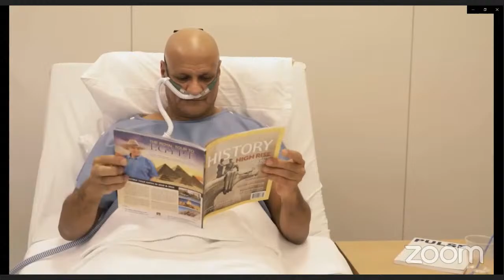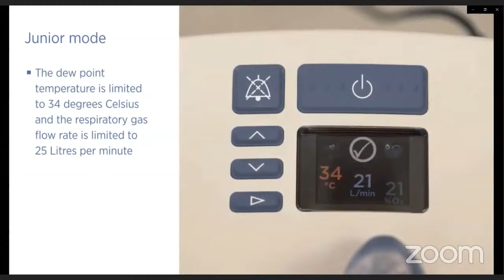If the patient will be using an Optiflow Junior nasal cannula, you must activate Junior mode. Press and hold the mode button for 5 seconds until the Junior mode symbol appears. The Evo 2 will automatically adjust the dew point temperature and gas flow to safe limits for the Junior interface. The dew point temperature is limited to 34 degrees Celsius and the respiratory gas flow rate is limited to 25 litres per minute. To deactivate Junior mode, follow the same procedure. Hold the mode button for 5 seconds.